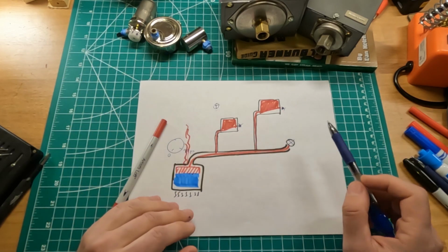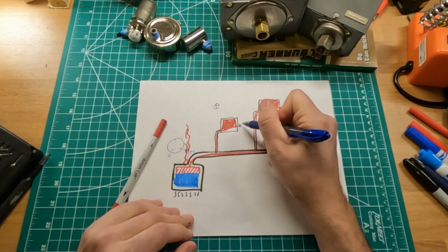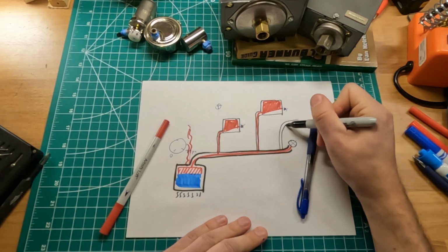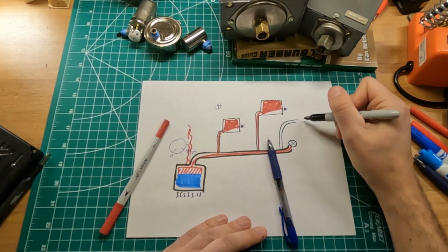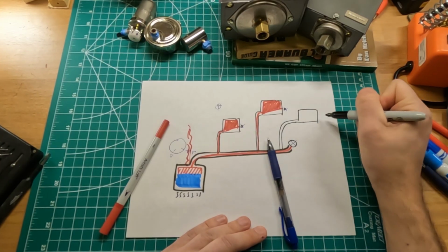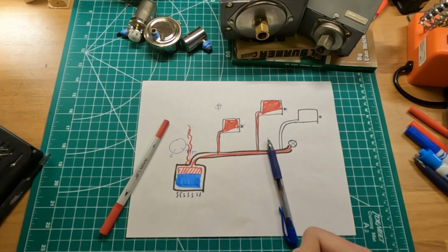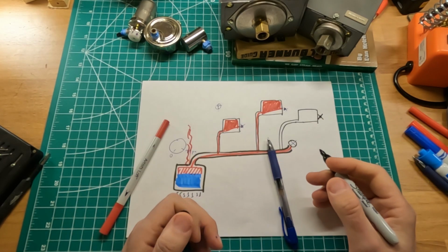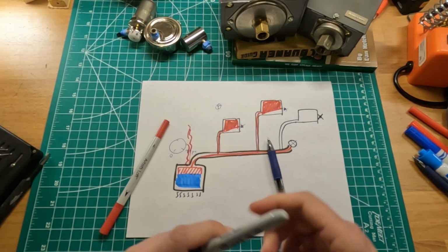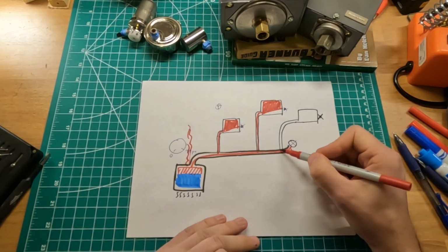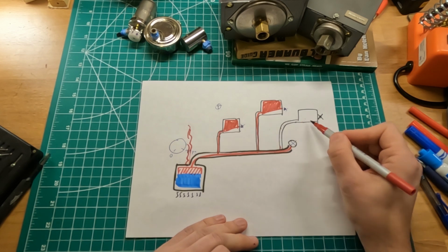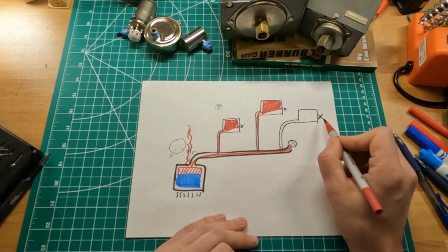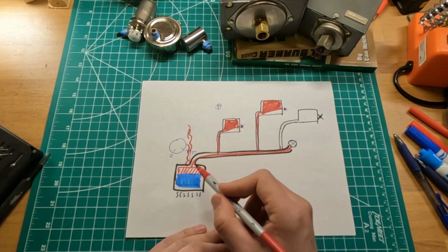another problem you can encounter is, let's say, one failing vent. Let's add another radiator to our schematics, so that we can see what happens. Let's add another vent here, and for the sake of discussion, let's assume that this vent is totally blocked, broken in a closed position. Because it's blocked, the air that's inside this pipe and inside this radiator can never escape through this vent. So because of that, this radiator will never get hot, and at the same time the pressure rises up.